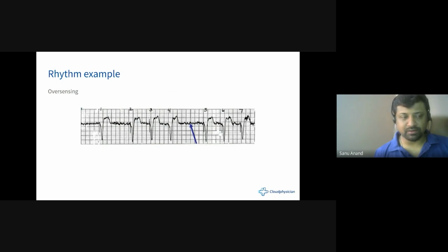Now, the opposite can happen, what is called oversensing, where the pacemaker senses a heartbeat even though the heart is not beating. Maybe the patient is dead, and there is just some nurse or doctor standing next to the patient and shaking the patient, or the BP cuff getting inflated, or any kind of vague activity which can be sensed as an actual heartbeat, and the pacemaker doesn't do anything. So you can see these long pauses here; there are two spikes, and even though there are no P waves anywhere, the pacemaker is not working at all. So this is called oversensing.